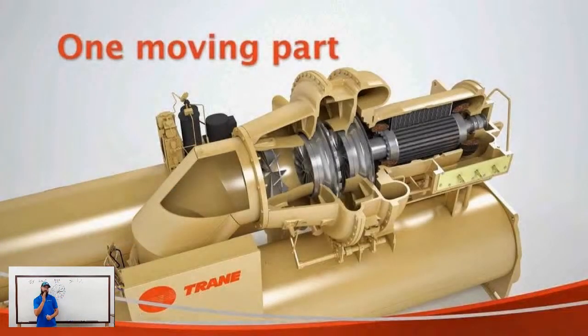So right there below where those IGVs are, on this chiller, you'll see there's an armature assembly on the outside of it that is not in the refrigerant stream. That is the IGV control armature. And there's an actuator attached to that that drives that arm up and down and swings it. And every manufacturer has their own basic version of this, but they all do the same thing. And that is how we're able to control it. And so you can literally look at that armature and see what literal position it is in visually.